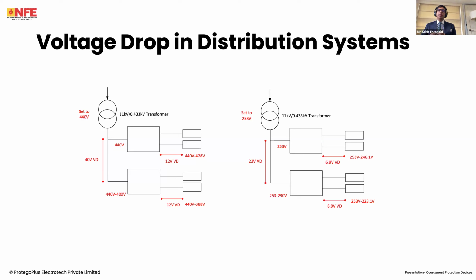Now, if you look at the standard 60038, it talks about plus minus 10%. So for a 400 volt circuit, plus 10% is 440 volts, minus 10% is 360 volts. For a 230 volt circuit, this becomes 253 volts and 207 volts. So what do we do?